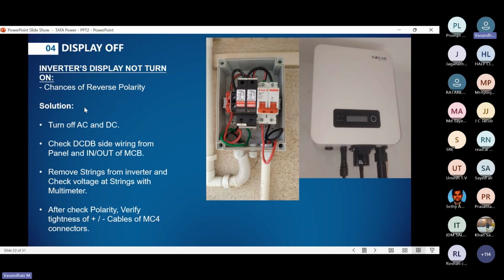So if the display is not on, here's what to check: turn off AC and DC, check the DCDB side to see whether the wiring is proper in and out of the MCB. Next, remove the PV strings and check the voltage to see how much we're getting against the rated input voltage. Then check the polarity and verify the tightness of the positive and negative MC4 connectors. These four steps we need to follow when the display doesn't turn on.